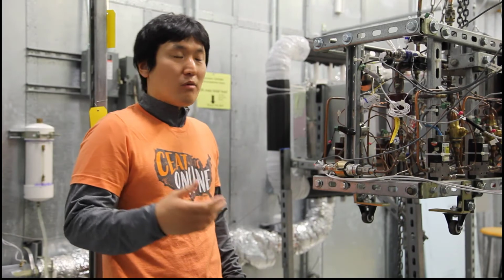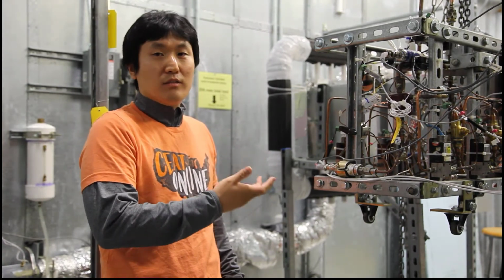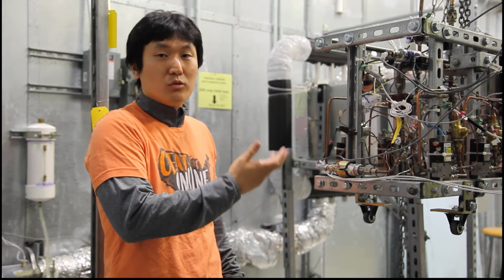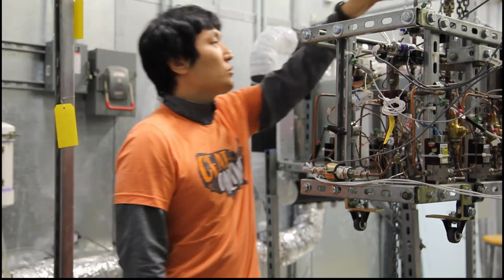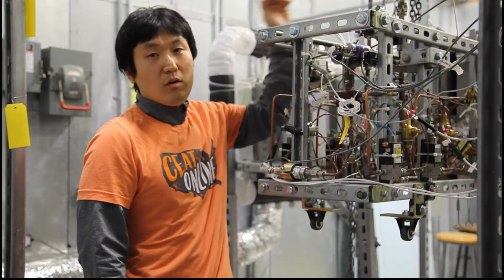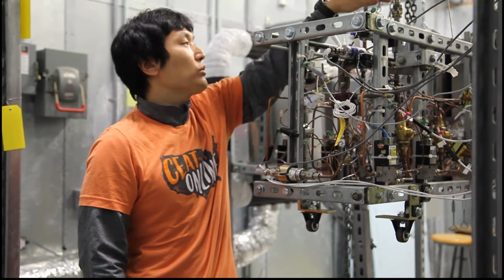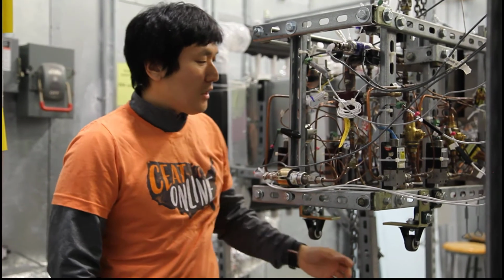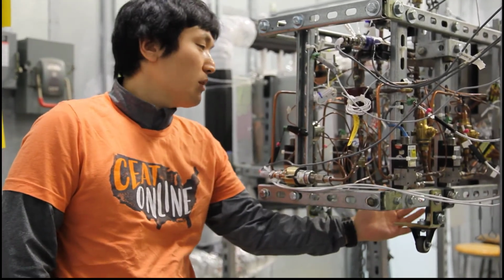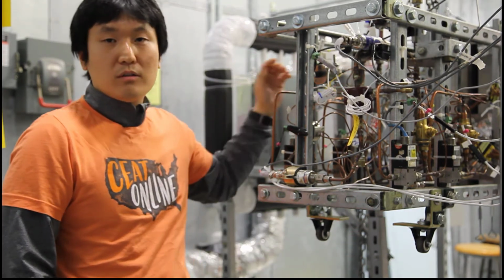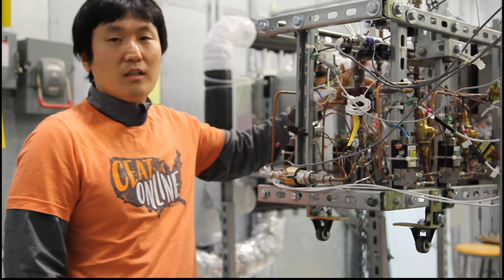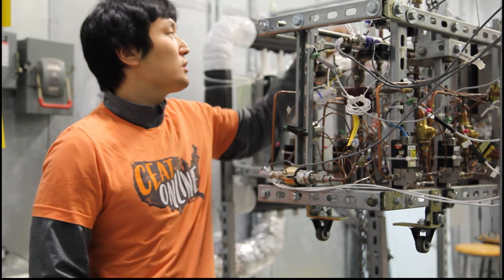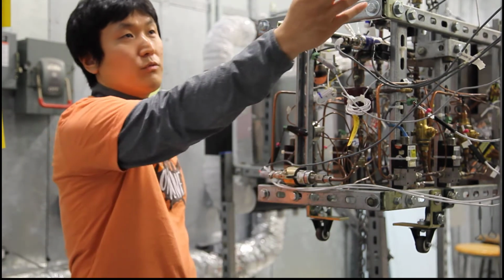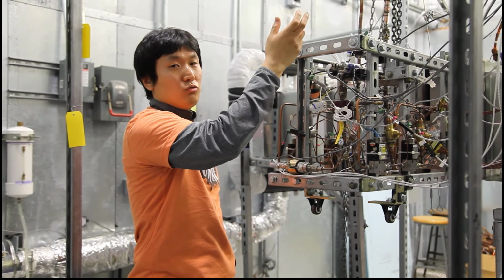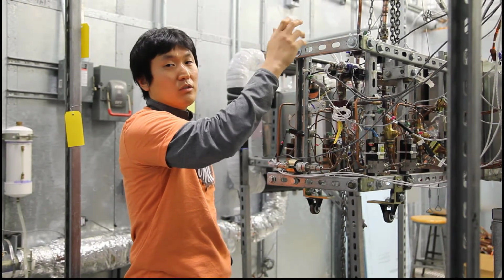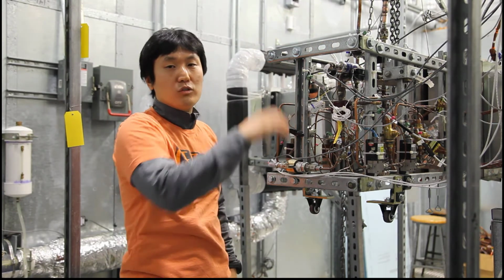Let me explain a little bit more about this RHXT. It stands for Removable Heat Exchanger Charge Test Module. Conditioned refrigerant is going through this module at the same time airflow is going through. So the refrigerant goes down through these pipes, and then there are 4 expansion valves, so the pressure is controlled, and then going through the test heat exchanger, and then the superheated vapor comes out through this pipe. So the conditioned refrigerant goes into the module, and then after the heat exchanger, the refrigerant goes back to the refrigerant loop.